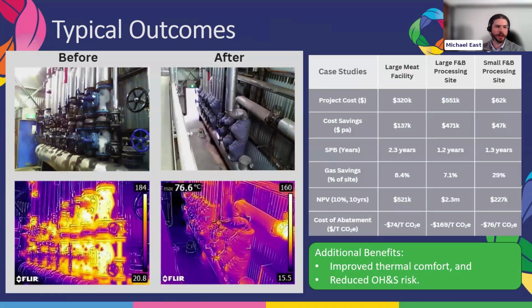So what does that start to look like when you pull it all together into the project? Here you can see before and after shots of a main header manifold in the corner of a boiler house. Beforehand, we've got temperatures on those valves at about 184 degrees. With the jackets on afterwards, that temperature has dropped right down to 76. More importantly, the surface area at that high temperature is greatly reduced - it's now just the areas where the spindle's going into the valve and the very edge of the jackets. Much of the rest of that jacket surface is way down at 20-odd degrees.